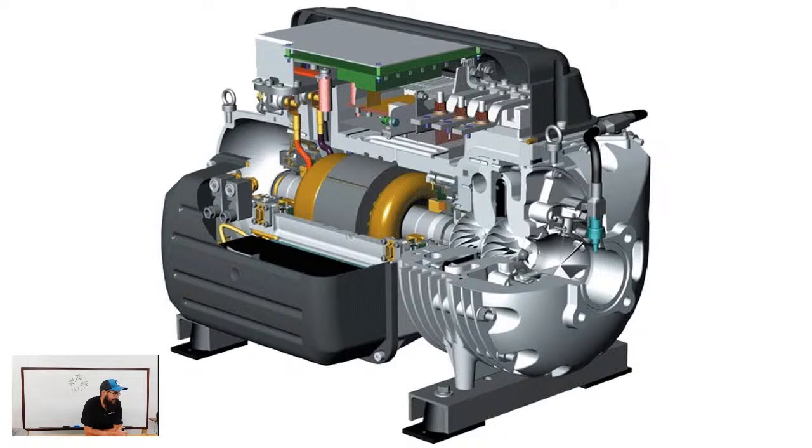Will manufacturing inconsistencies affect reliability with the complexity of the Turbocor though? Yes, they do. So for example, Smardt, in my opinion, is not my favorite line of machines and their control systems. While they work, they do work. Not a fan of their setup. And it's not Turbocor that's the problem, in my opinion. The Turbocor I've seen, you have to connect via the laptop to have compressor data.